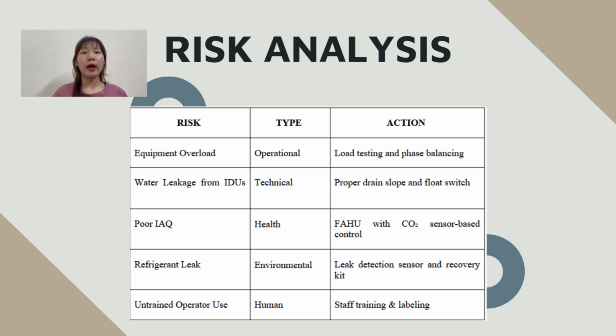Poor indoor air quality, or IAQ, is a health risk. Here, we suggest using FAHU, fresh air handling unit, integrated with CO2, carbon dioxide, gas sensor-based control to maintain safe air quality levels. Refrigerant leak falls under environmental risk. The right countermeasure is installing a leak detection sensor and keeping a recovery kit available to manage any spills. Lastly, we have untrained operator use, which is a human risk. The solution is straightforward: ensure through staff training and proper labeling of system and equipment. This structured risk assessment helps us ensure that each area of concern is backed by clear preventive actions, enhancing both safety and operational efficiency.